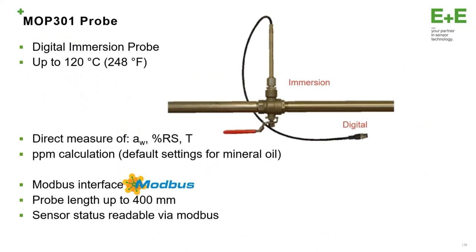The MOP 301 is a digital immersion probe because you can install the probe directly inside the transformer. The probe is compact and inside there is a digital interface. This probe works up to 120 degrees Celsius. We have direct measurement of water activity, relative saturation, and temperature. The digital interface is Modbus RTU with RS485 interface. We have two probe lengths: 200 millimeters and 400 millimeters, which allow placement at different positions in the transformer.